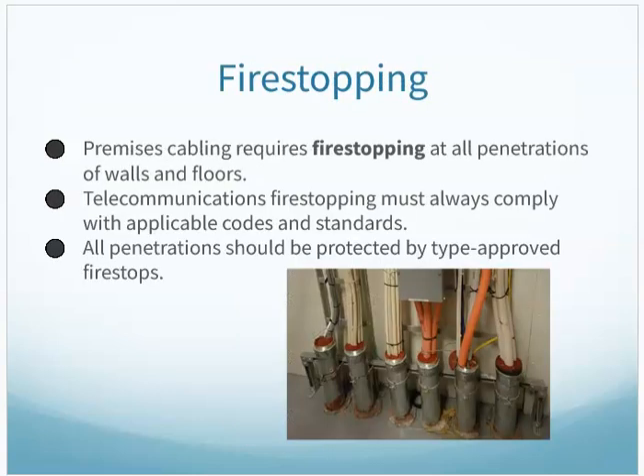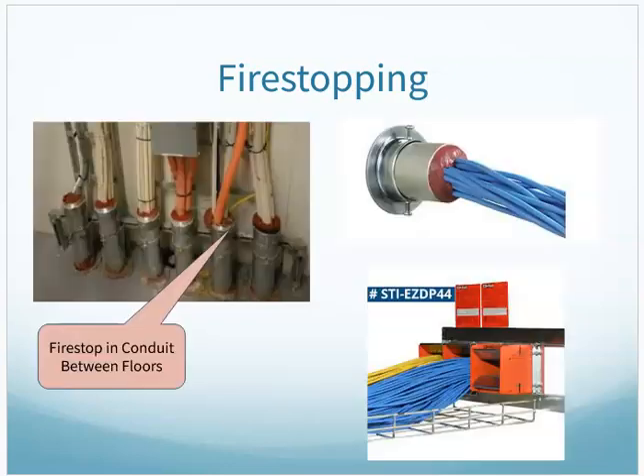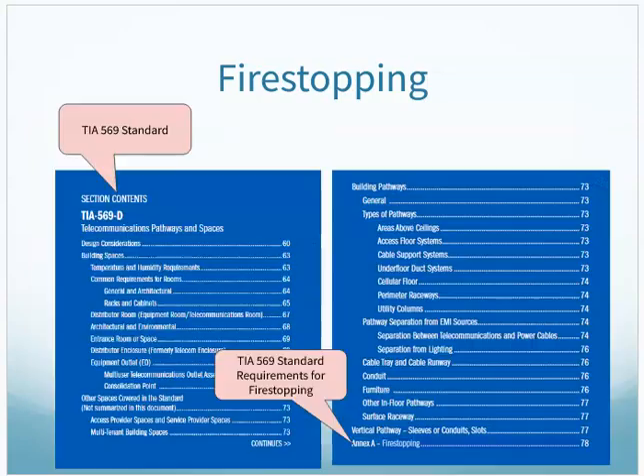We said before about fire stopping. We need to make sure, as we have conduits through walls and or floors, that we have plans for how we are going to fire stop that equipment. Here's a conduit with your fire retardant clay, if you will, that goes in there for fire stopping. But they also make fire stopping mechanical hardware that can get used as well. And here's your 569 standard on what's required for fire stopping.